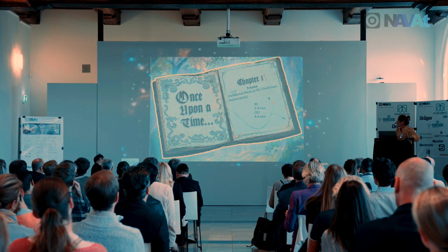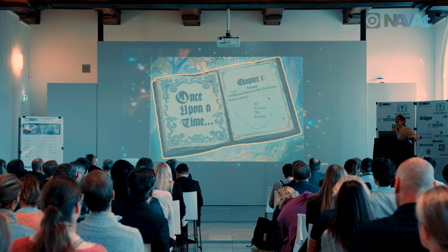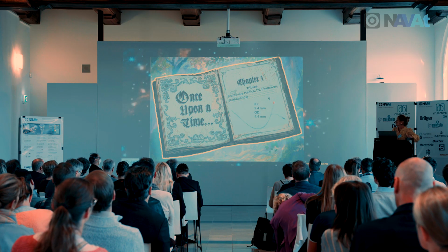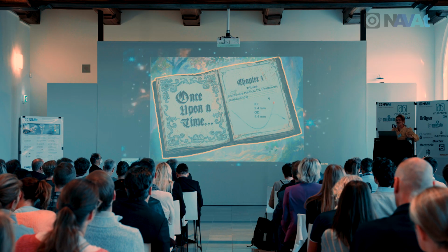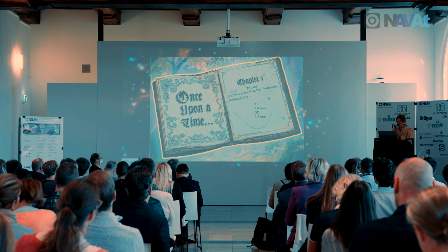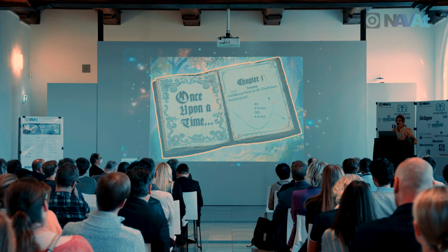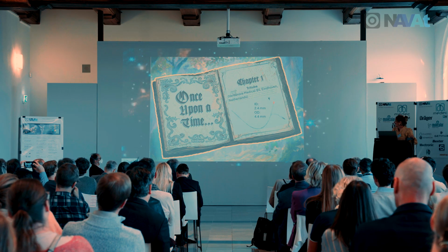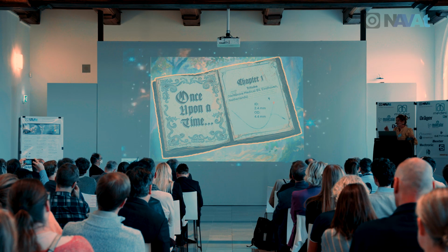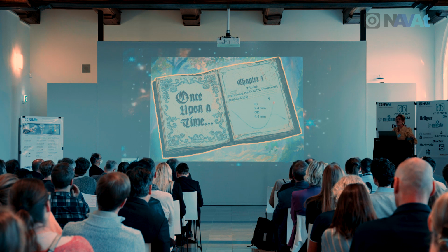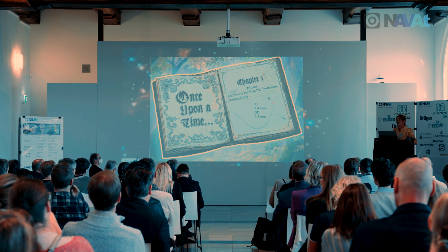Now, where did the story start? It all started with the design of a very special single lumen tube, the Tritube. This is a single lumen tube with a very small diameter, and it was specially designed for use during tracheal surgery. The diameter of this tube is so small that passive expiration is not possible anymore.